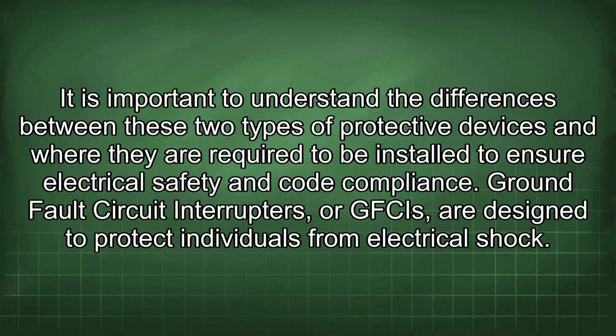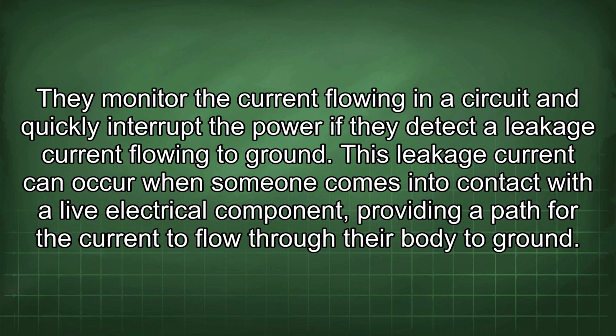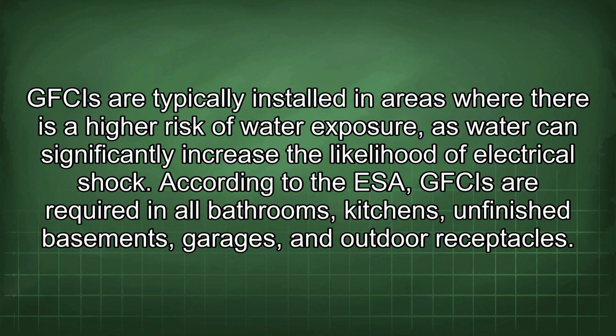Ground fault circuit interrupters, or GFCIs, are designed to protect individuals from electrical shock. They monitor the current flowing in a circuit and quickly interrupt the power if they detect a leakage current flowing to ground. This leakage current can occur when someone comes into contact with a live electrical component, providing a path for the current to flow through their body to ground. GFCIs are typically installed in areas where there is a higher risk of water exposure, as water can significantly increase the likelihood of electrical shock.